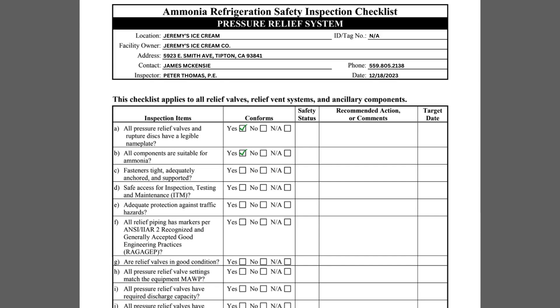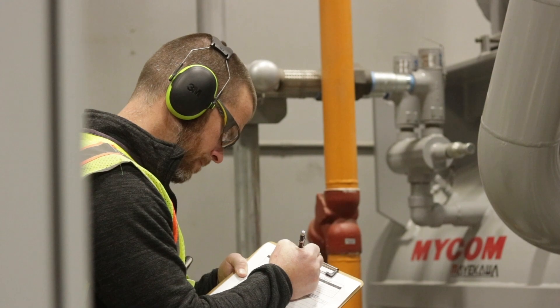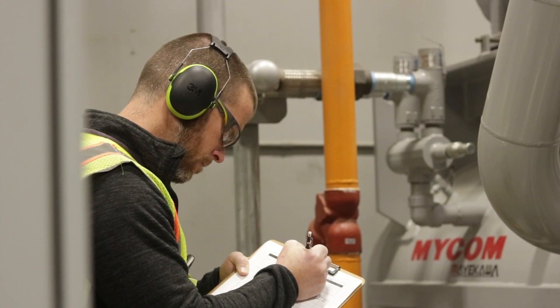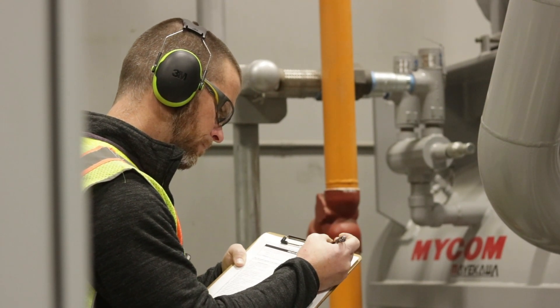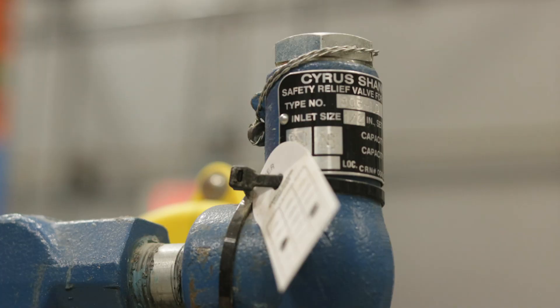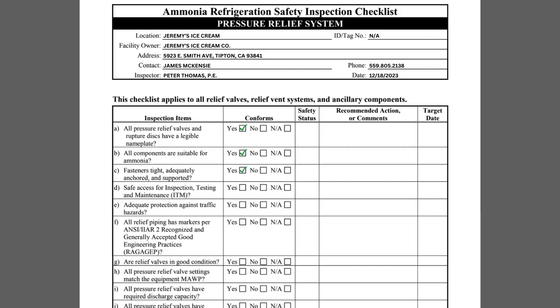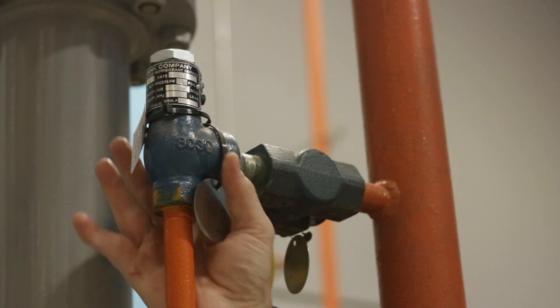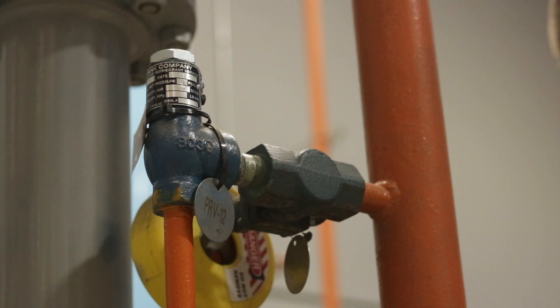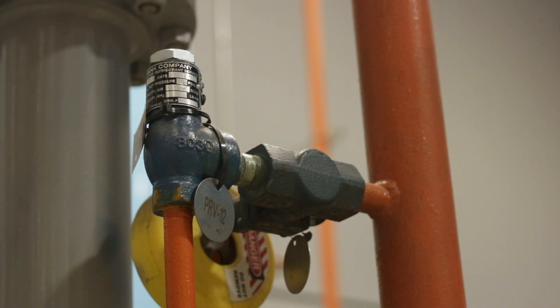Item B asks if all the components in the relief system are suitable for ammonia. Suitability for ammonia can be verified by the equipment specifications provided by the manufacturer. Pressure relief valves supplied by reputable manufacturers will satisfy this requirement. Item C requires the inspector to verify that supports and anchorage are adequate. While relief valves are not typically anchored, this question provides an opportunity for the inspector to assess the discharge piping to make sure that it is adequately supported.